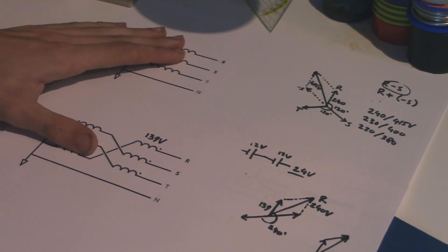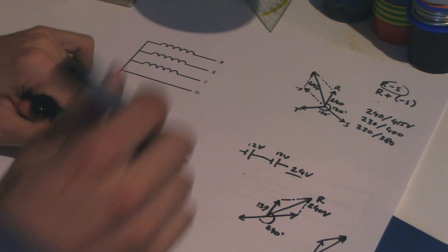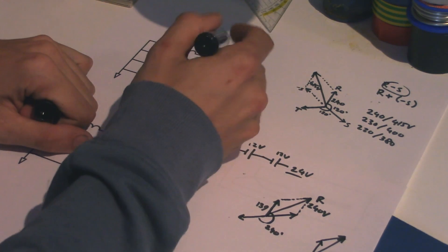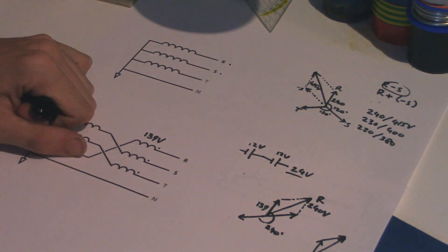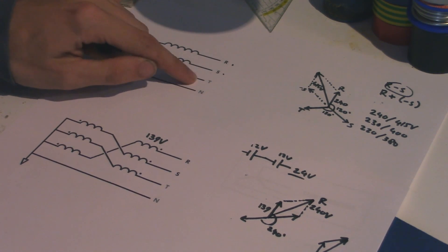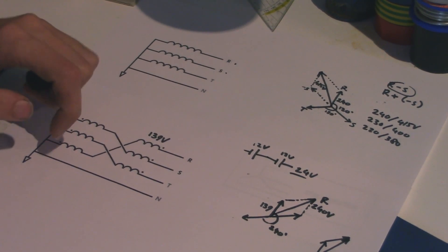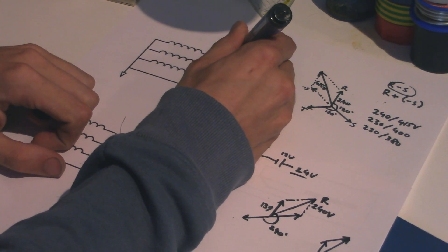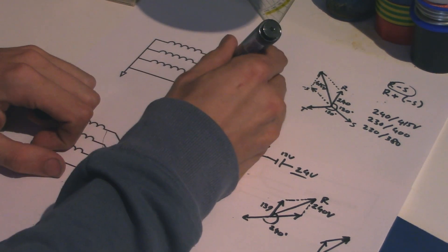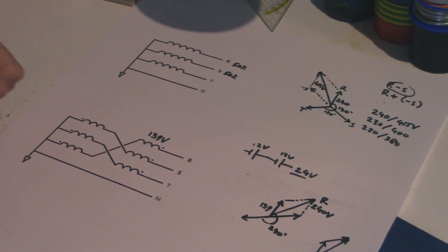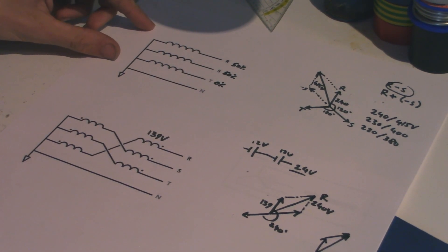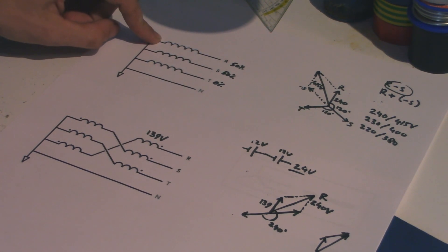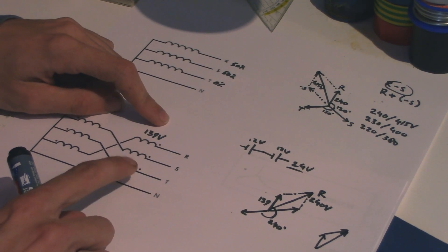So in order to understand that, let's take a very extreme example. Let's say we have a situation with maximum load on R. So we're going to put a dot next to R, maximum load on S as well, I'm going to put a dot next to that as well, and nothing on T. So for some reason, no one is using this phase. Of course, in the real world, it's not going to happen, but again, extreme example. So what that means is we have 50% of the load on R, and 50% of the load on S, and 0% on T. And on our transformer, that is exactly the same. This leg of the transformer is used to the max, and so is this one, and this one is unused.